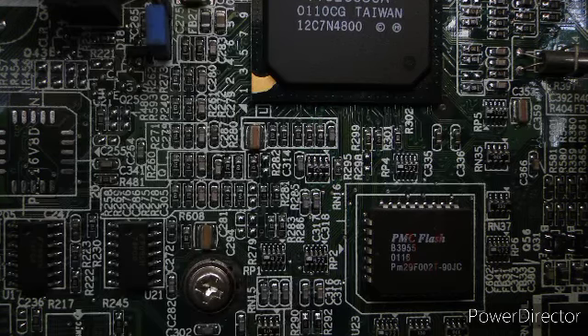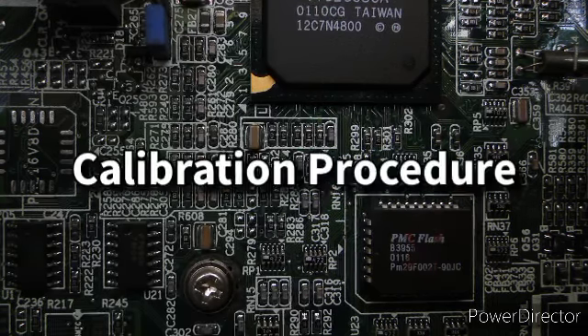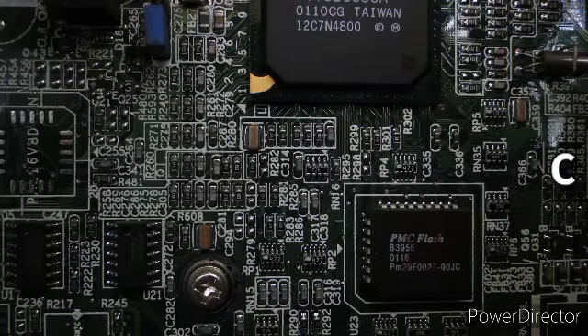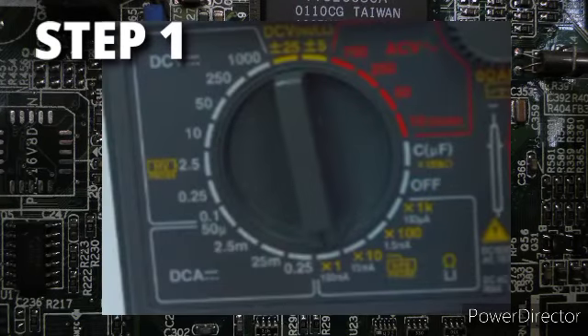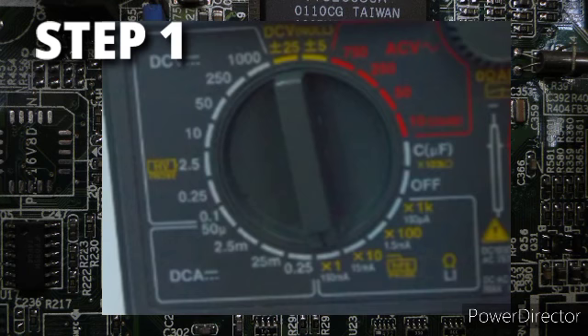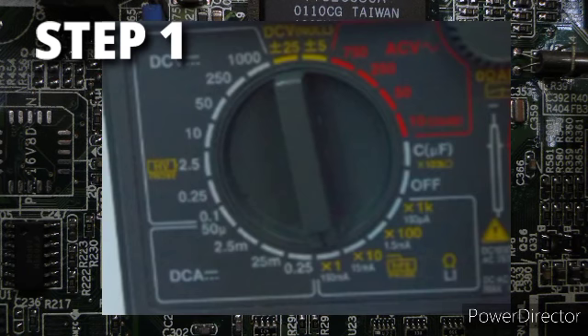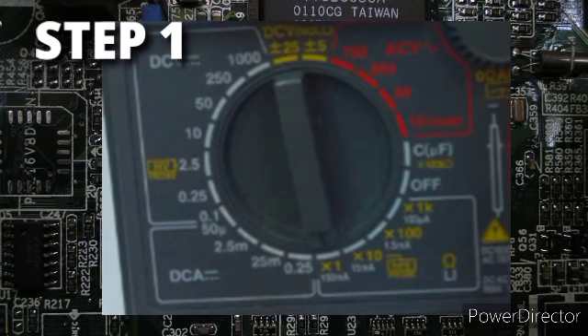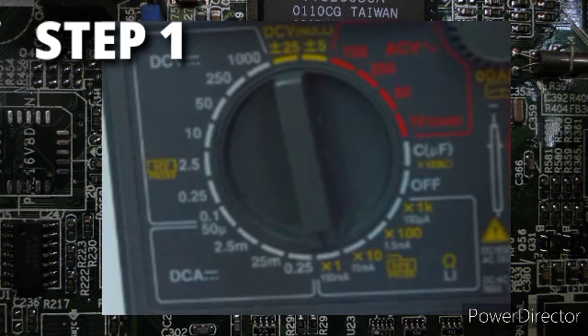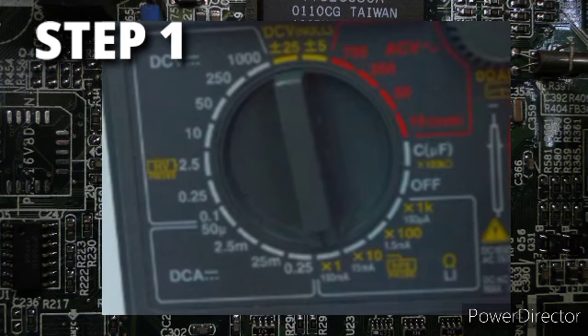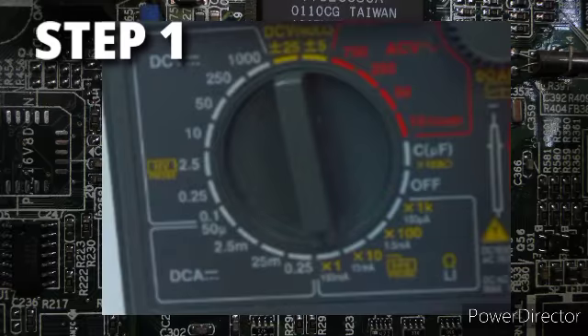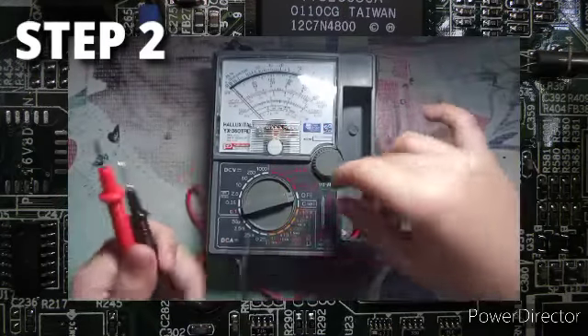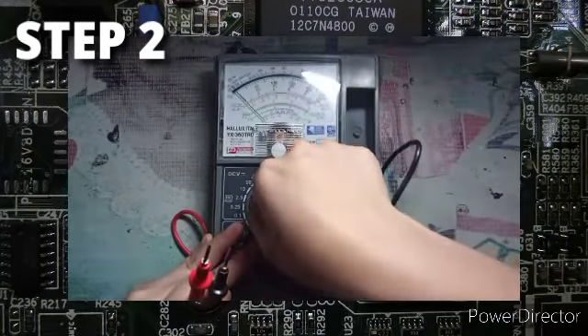Now, let us proceed to the calibration procedure. Step 1. Set the multimeter to its ohmmeter function. It is located at the lower right portion of the selector knob. We can see that there are multipliers. These multipliers are used to increase or change the scaling of the ohmmeter for better resolution. Step 2. Set the selector knob to multiplier times 1.